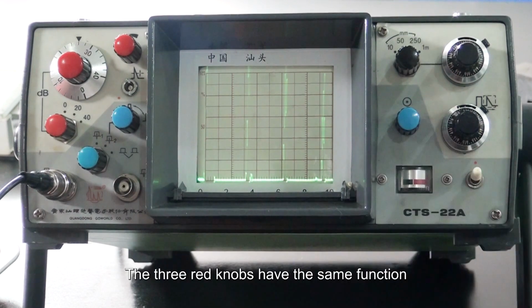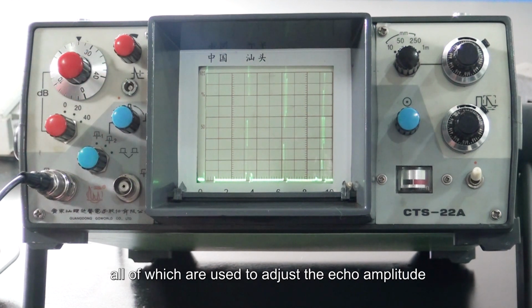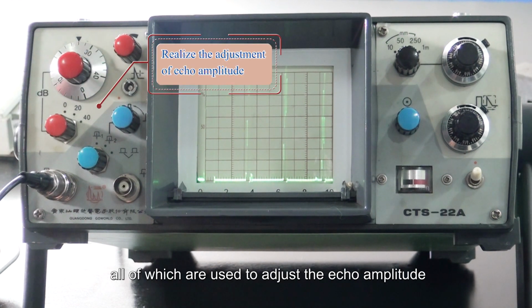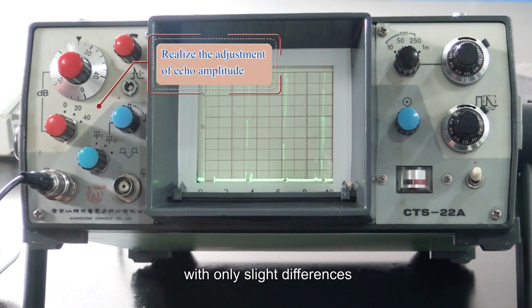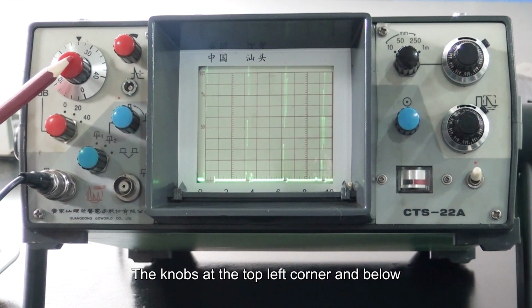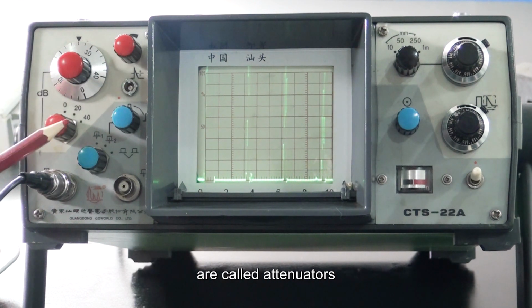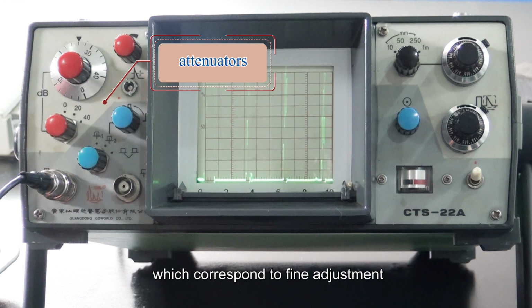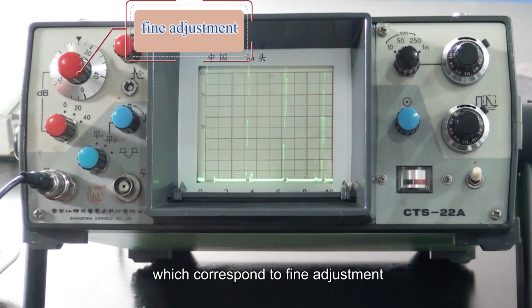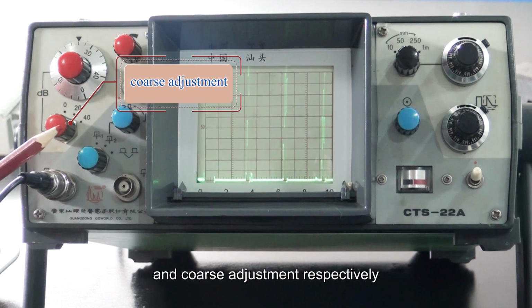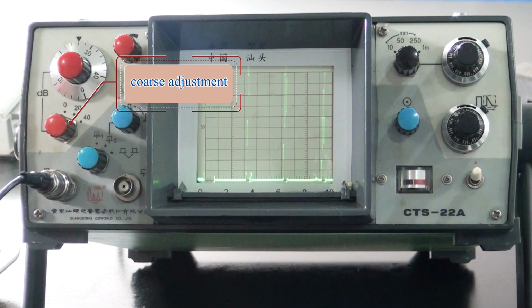The 3 red knobs have the same function, all of which are used to adjust the echo amplitude, with only slight differences. The knobs at the top left corner and below are called attenuators, which correspond to fine adjustment and coarse adjustment respectively.